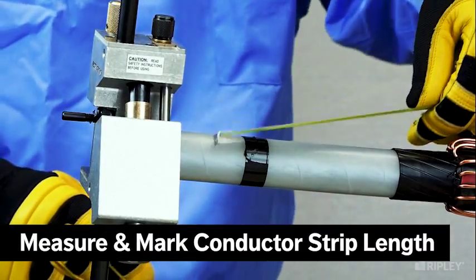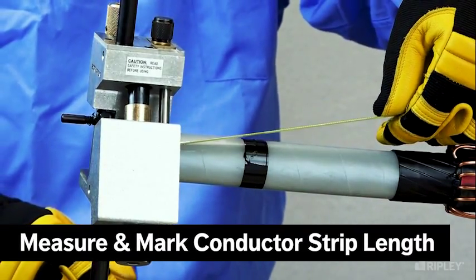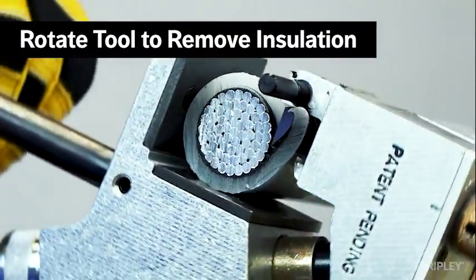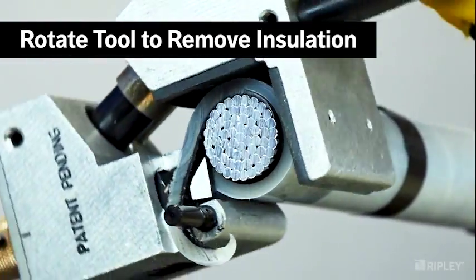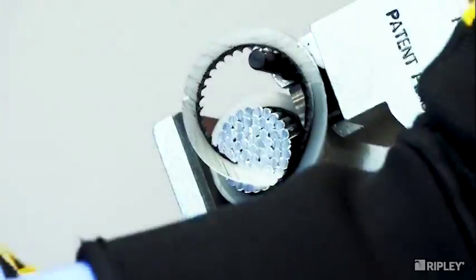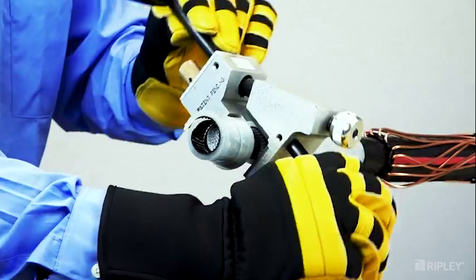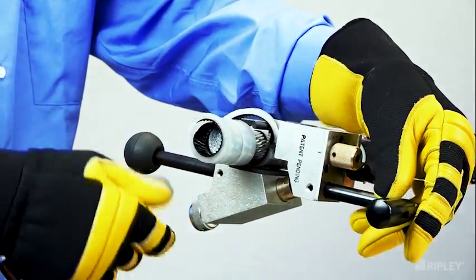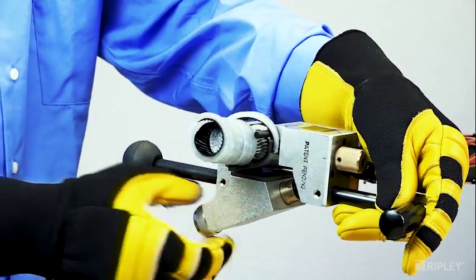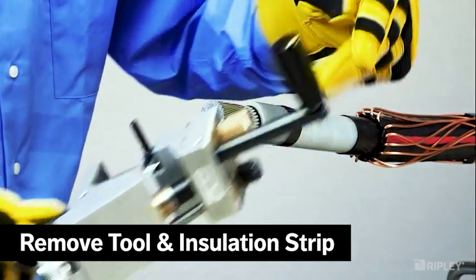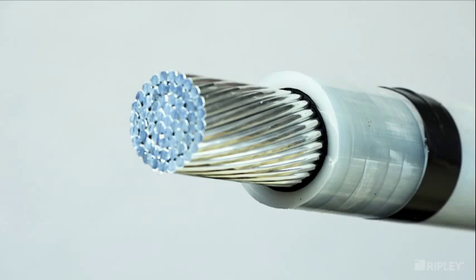Measure and mark the intended conductor length. Rotate the tool around the insulation layer until reaching the mark. Reset the blade to 0 degrees and rotate the tool once around the insulation to achieve a squared edge. Release the tool from the cable and remove the insulation strip to complete the end stripping process.